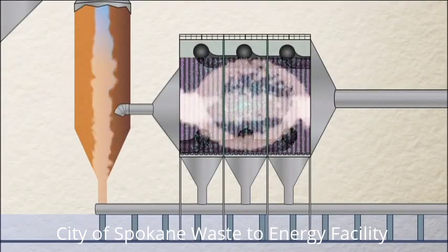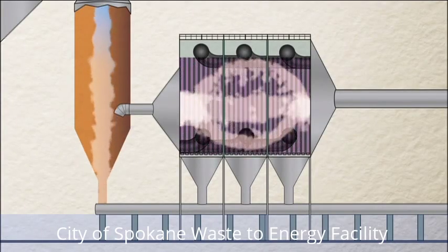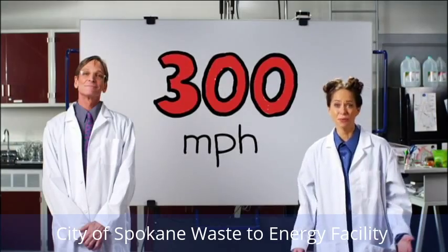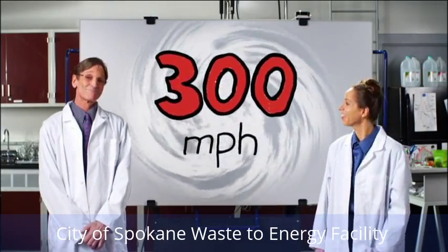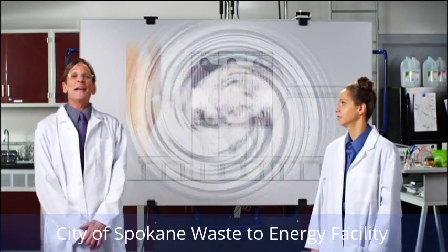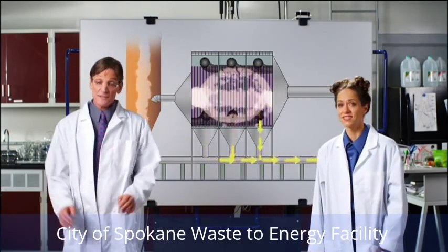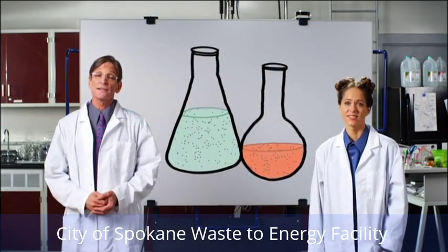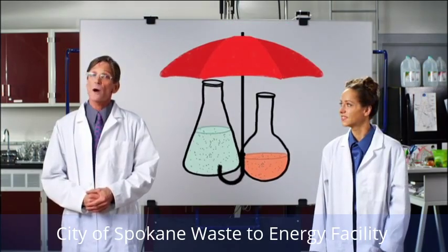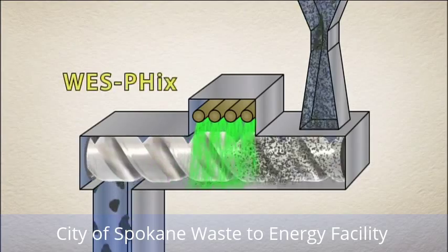There's more work to be done with the fly ash captured in the bag house. The ash is blasted out of the bags every couple of minutes by a burst of air moving at 300 miles per hour — about twice as fast as a major hurricane. That air forces the fly ash out and down into a closed conveyor. There are still heavy metals in the ash at this point, and because it's headed to a landfill, it's important that the metal particulates won't wash out in rainwater. That's why the ash is treated with a reagent in a process called WES-PHix, which changes the metal back to a natural ore-like state.